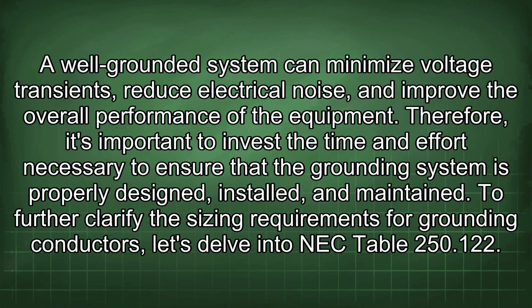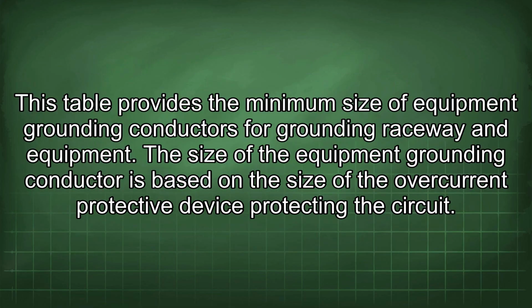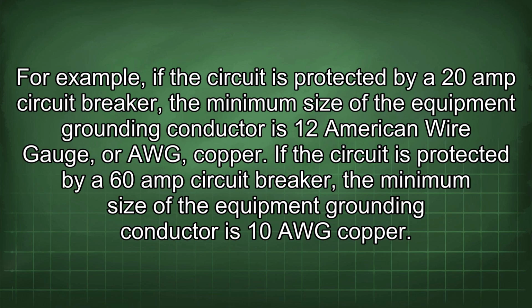the equipment. Therefore, it's important to invest the time and effort necessary to ensure that the grounding system is properly designed, installed, and maintained. To further clarify the sizing requirements for grounding conductors, let's delve into NEC Table 250.122. This table provides the minimum size of equipment grounding conductors for grounding raceway and equipment. The size of the equipment grounding conductor is based on the size of the overcurrent protective device protecting the circuit. For example, if the circuit is protected by a 20 amp circuit breaker, the minimum size of the equipment grounding conductor is 12 American wire gauge or AWG copper.